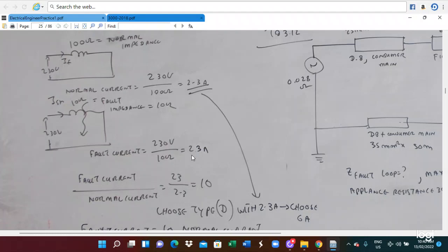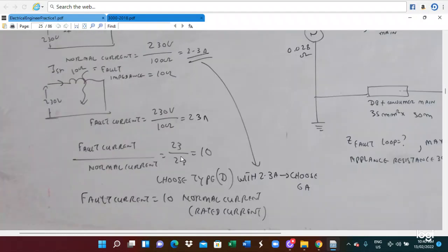Then we have to find the ratio between the normal current and the fault current. The normal current is 2.3 ampere, the fault current is 23. Dividing 23 by 2.3, you get 10. So this ratio is 10. Now we have to find out what kind of circuit breaker is suitable: type B, type C, or type D.